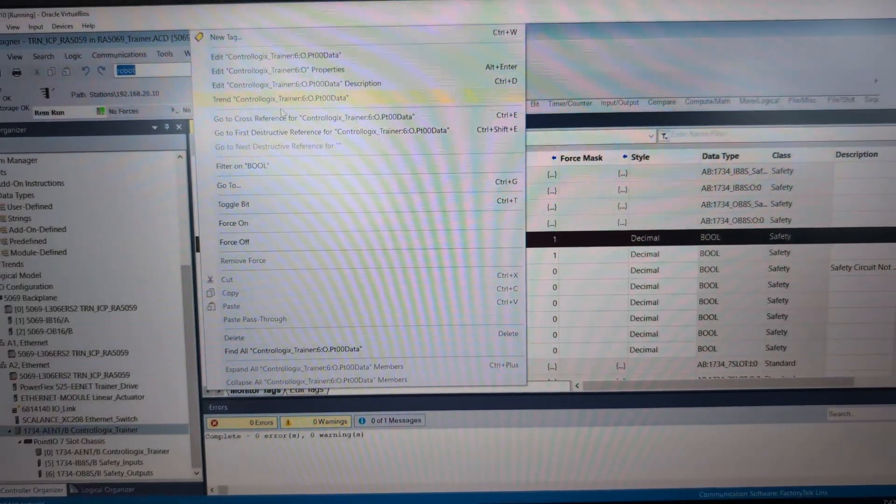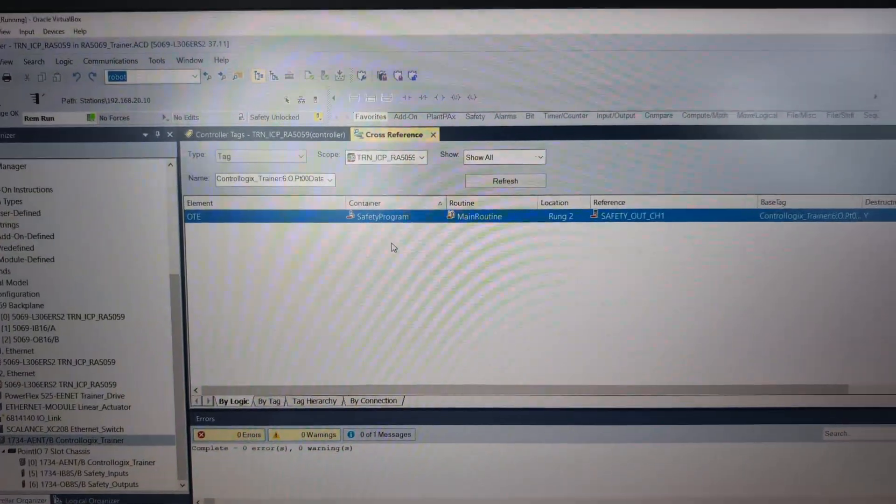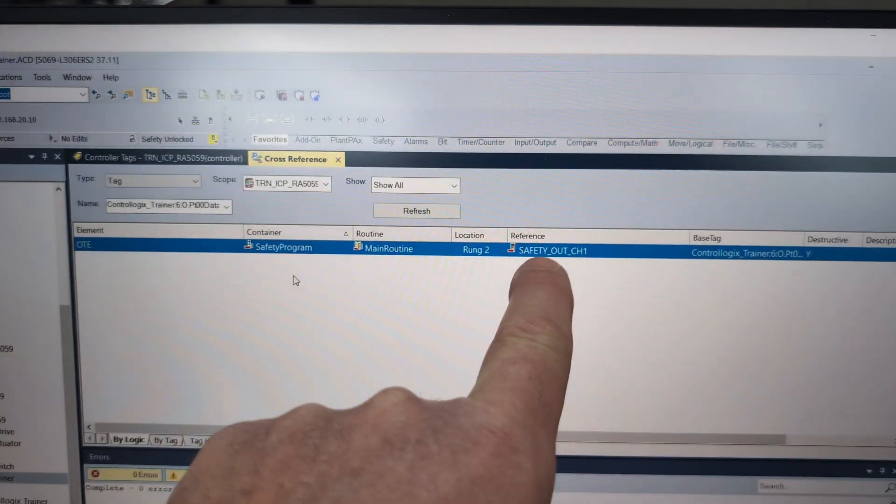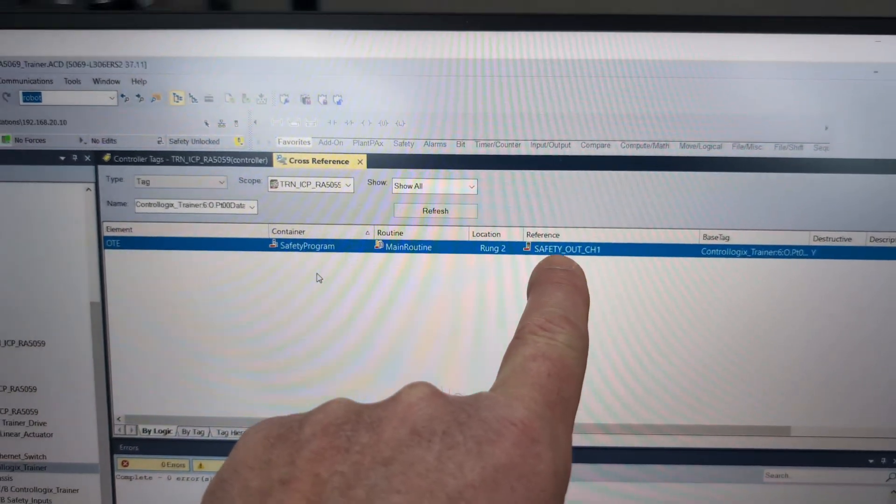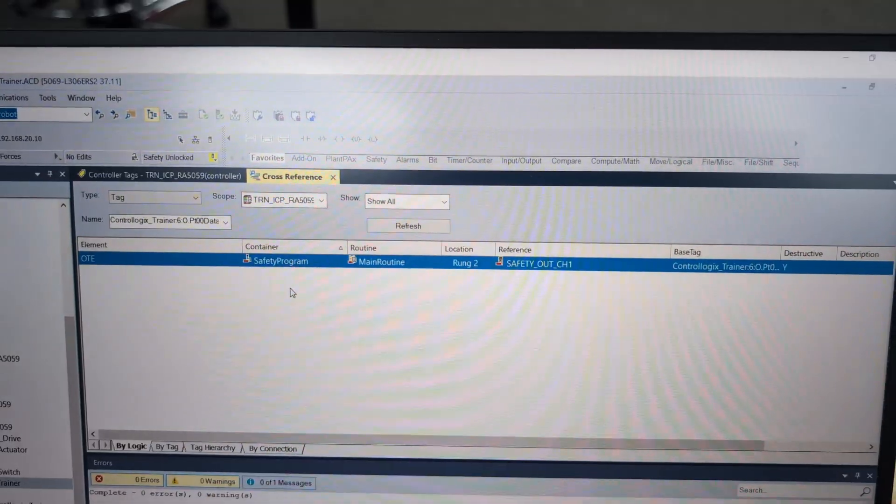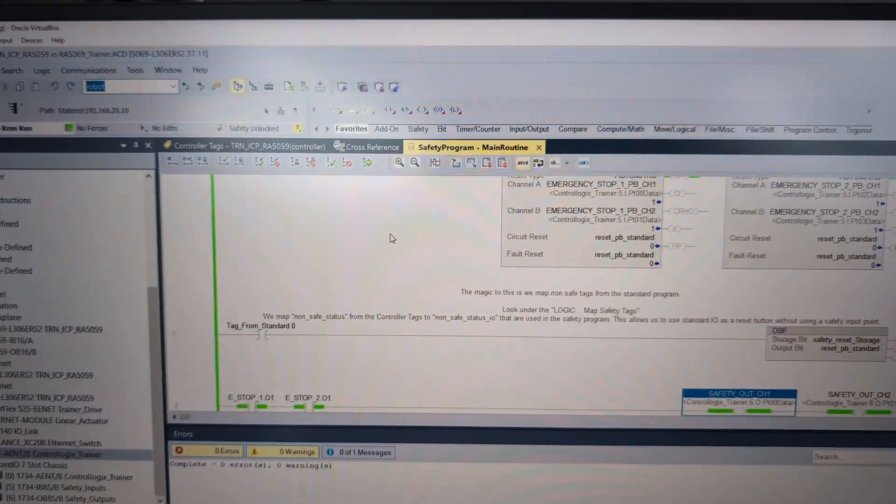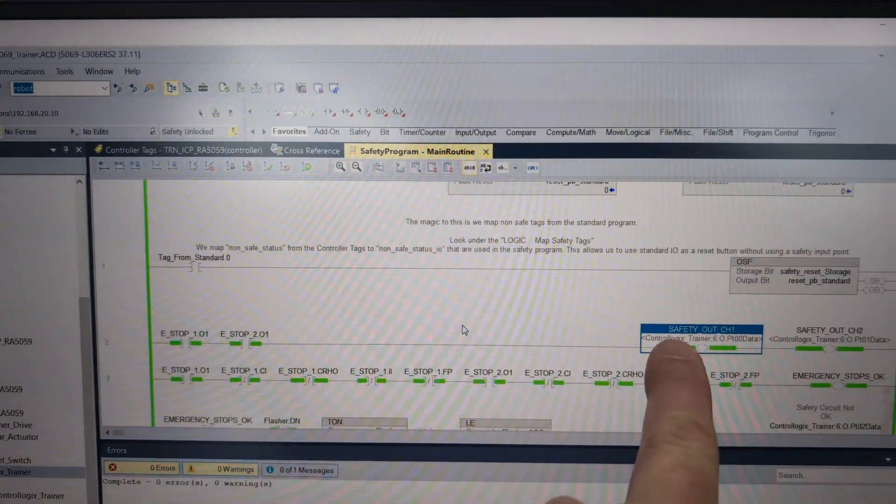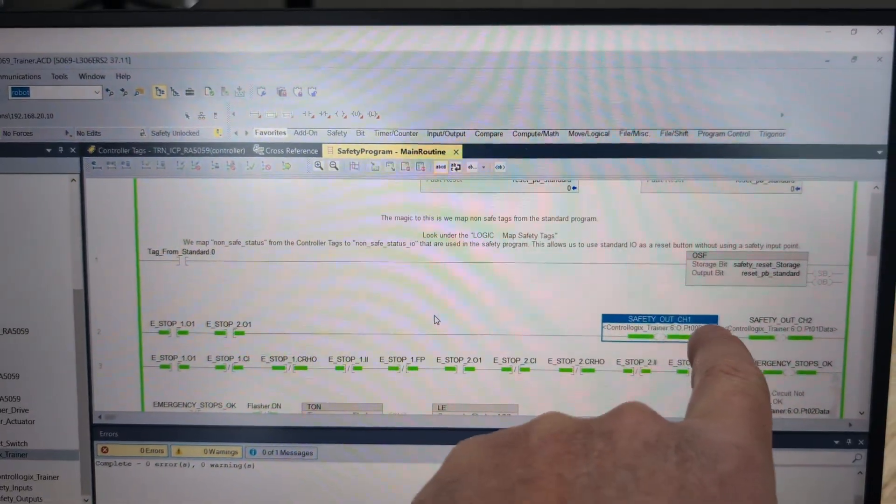And so if we simply had a description there, then this would be much easier to find. And this is probably the number one thing I found in programs that are heavily aliased. There's no descriptions on the actual I/O points. We would have to hunt and peck through each one of these, which I'll cross reference the first one. And only now, and even then, it's not going to jump out at us. Only now are we going to realize this is safety_out_channel_1.